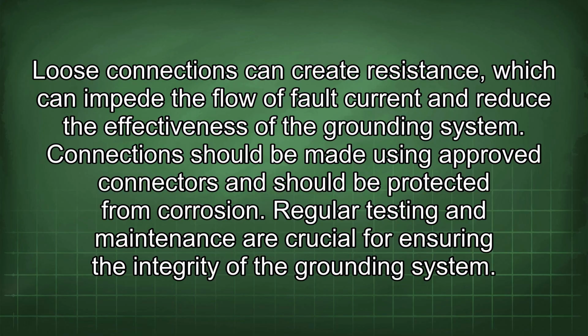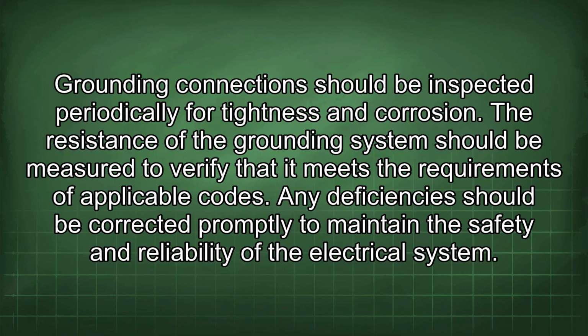Regular testing and maintenance are crucial for ensuring the integrity of the grounding system. Grounding connections should be inspected periodically for tightness and corrosion. The resistance of the grounding system should be measured to verify that it meets the requirements of applicable codes. Any deficiencies should be corrected promptly to maintain the safety and reliability of the electrical system.